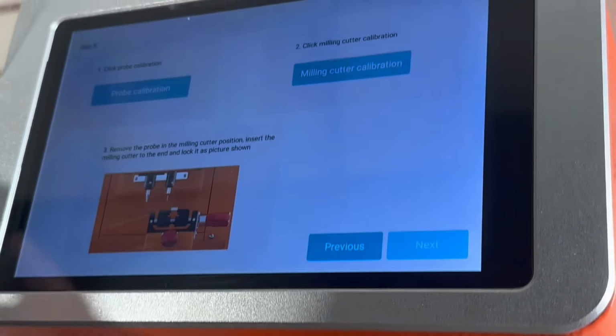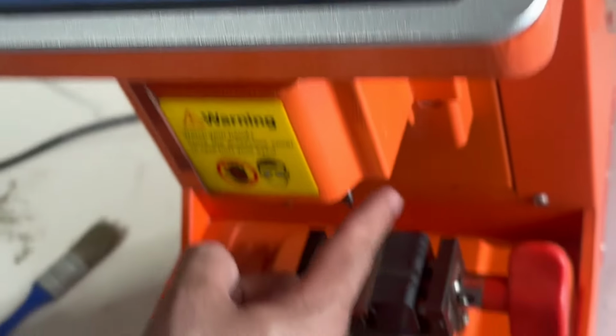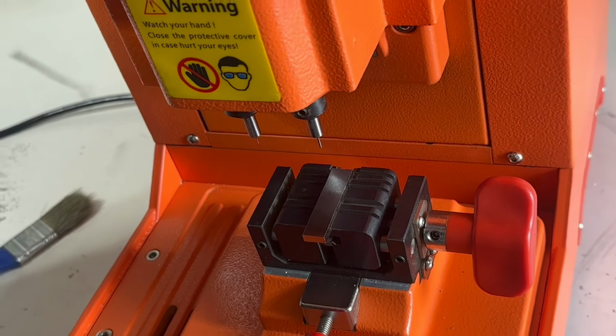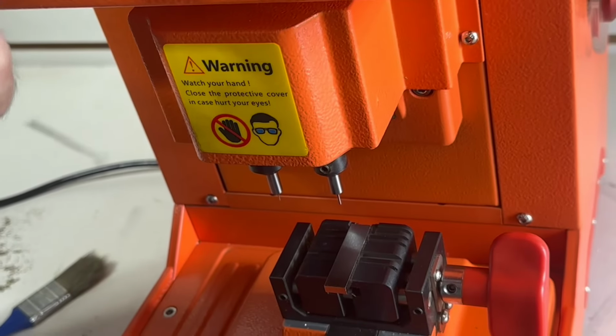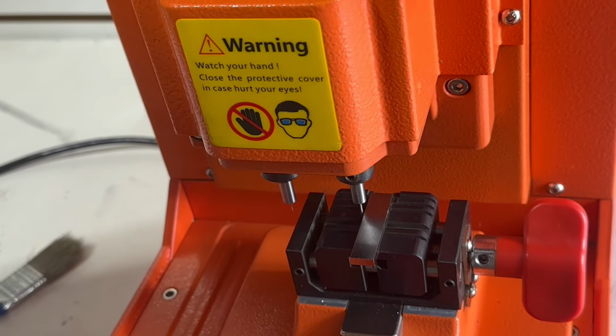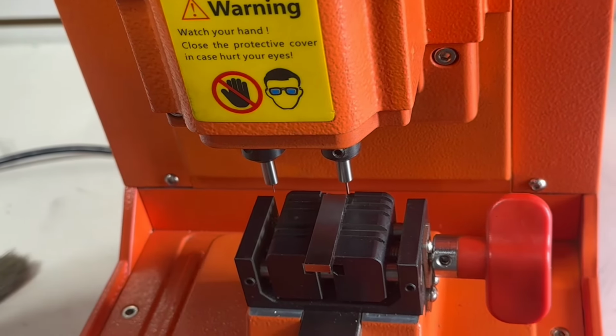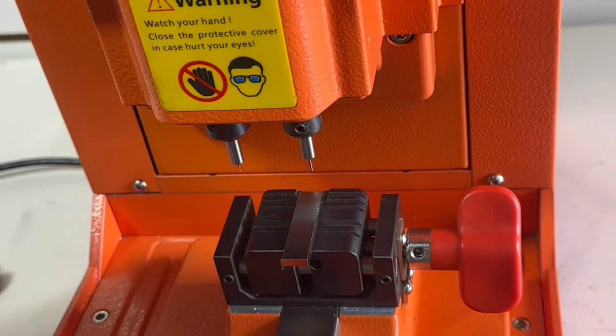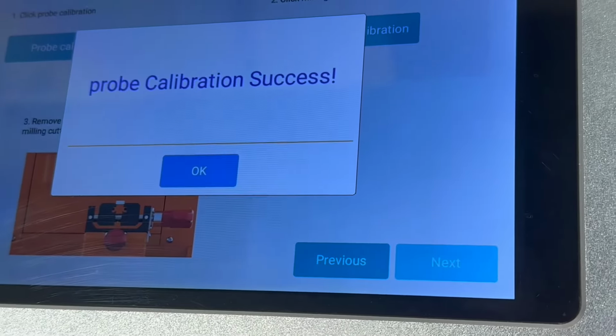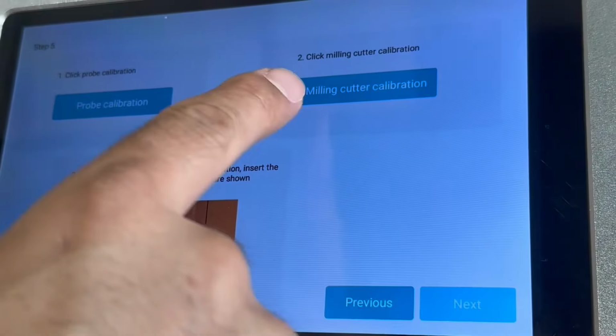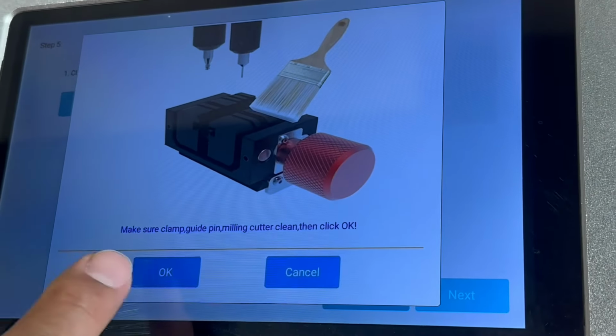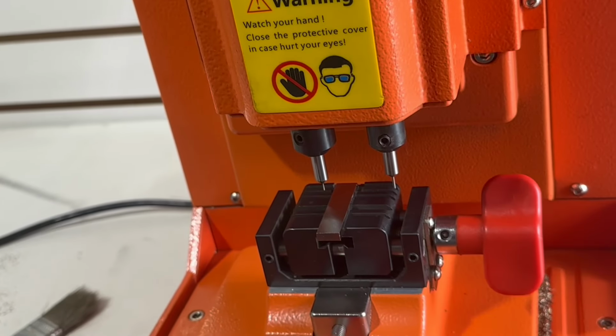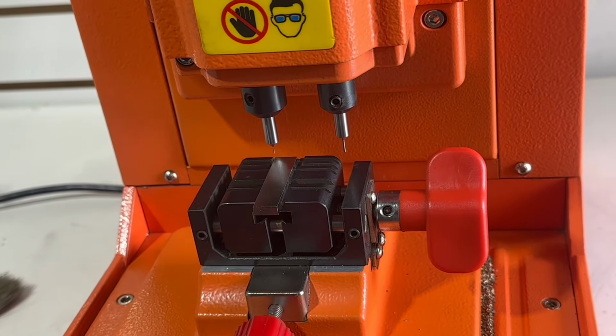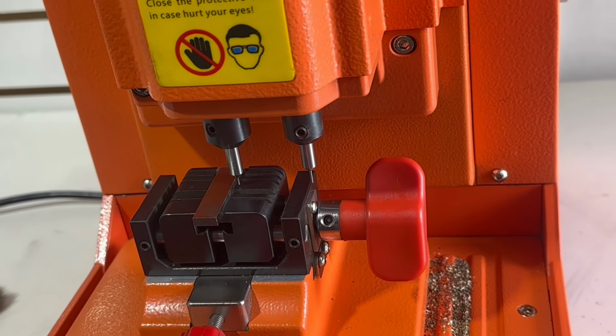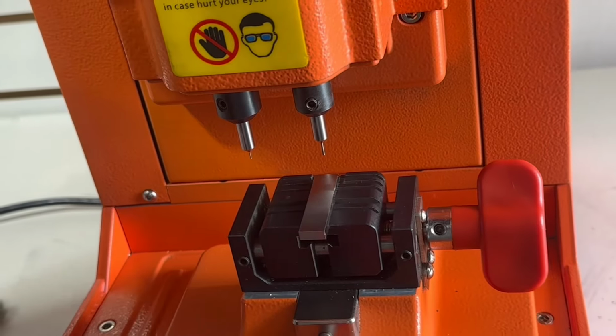So we're going to the next step now. It says click probe calibration. So we're calibrating the probe here. So once you click, and then you have to press OK to confirm. So it's gonna go and it's gonna calibrate. So it does all around calibration to get a precise measurement. So now you see the screen says calibration success. You press OK. Now step 2 is the calibrating the milling cutter. So is the blade. So you're gonna press OK again, and it will do the same step for your milling cutter, which is now a probe in there. So now you see success for that as well.